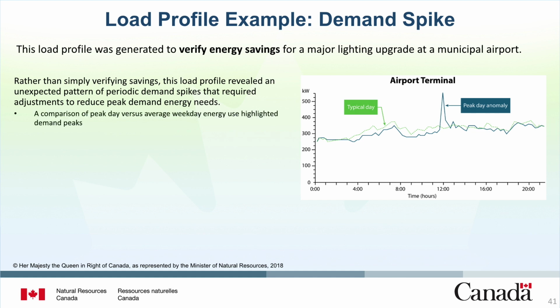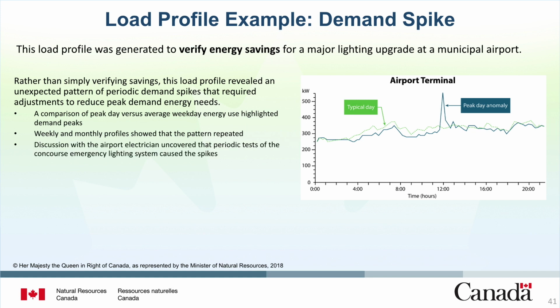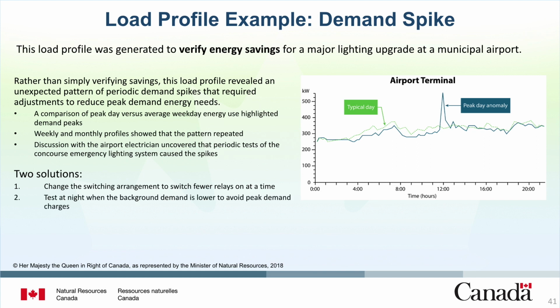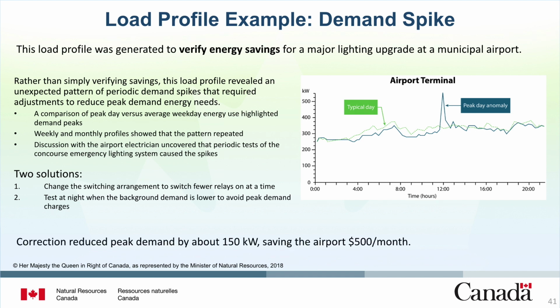A comparison of peak day versus average weekday energy use highlighted demand peaks. Weekly and monthly profiles showed that the pattern repeated. Discussion with the airport electrician uncovered that periodic tests of the concourse emergency lighting system caused the spikes. Two solutions were apparent. Either change the switching arrangement to switch fewer relays at one time, or test at night when the background demand is lower to avoid peak demand charges. This correction reduced peak demand by about 150 kilowatts, saving the airport $500 per month.